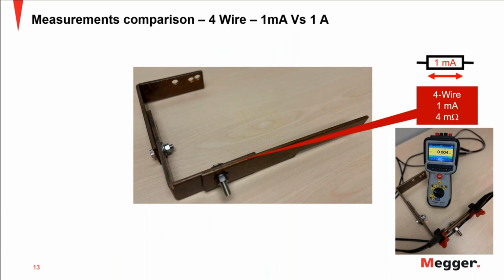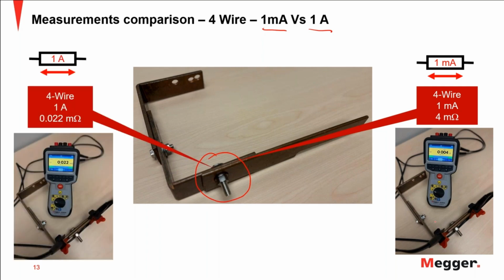One more comparison, the 1 milliamp measurement with the four-wire method versus 1 amp. So now basically it's the same connection that I'm going to measure. It's going to be the same instrument with the same method, the four-wire method. The only change is that now we have higher current. And with 1 amp, we have a result of 0.022 milliohms. So from 4, we went to 0.022. That is almost the 4 milliohms difference, 3.978, and almost 200% difference, with the same instrument, just changing the amount of current.